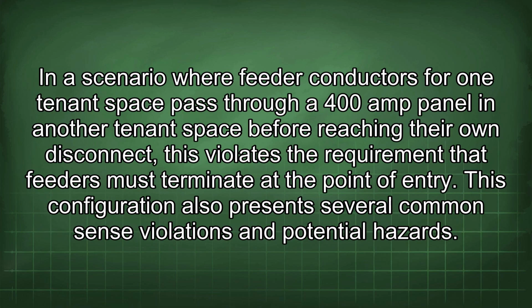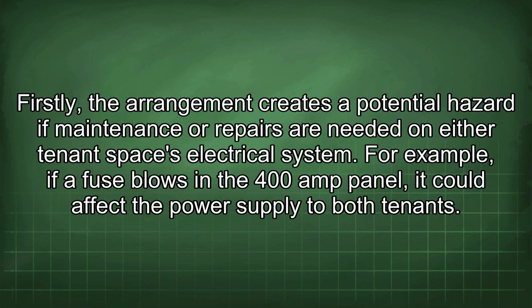In a scenario where feeder conductors for one tenant space pass through a 400 amp panel in another tenant space before reaching their own disconnect, this violates the requirement that feeders must terminate at the point of entry. This configuration also presents several common sense violations and potential hazards. Firstly, the arrangement creates a potential hazard if maintenance or repairs are needed on either tenant space's electrical system. For example, if a fuse blows in the 400 amp panel, it could affect the power supply to both tenants.